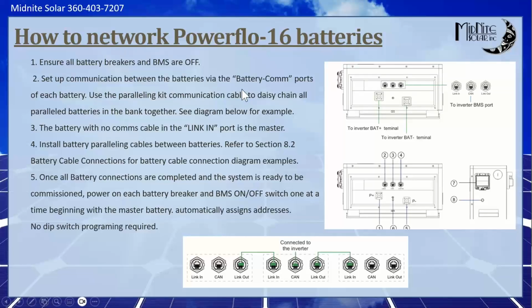Same kind of mentality. Everything's off, all breakers are off. You plug your link in to link out cables down through your stack of batteries, and you plug in your closed loop cables like you normally would. No programming needed. Then when you're ready to turn it on, same process: turn the breakers on, press the power button on the master battery, and then turn your inverter on.